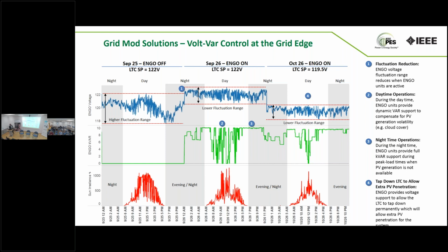So what they did here is: okay, the ENGO is deployed, but it's off. And here is the PV plant production, and this is what was happening with voltage in that specific location where the ENGO was installed - there was a higher voltage fluctuation range.